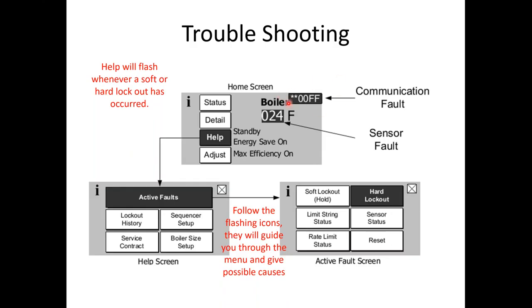But this one is a communication fault, and unfortunately, it's a 50-50 shot. It's either the control stopped talking to the display, or the display stopped talking to the control. In some rare occasions, it's the harness is loose. In some rare occasions, the harness, especially if it happens right out of the box in shipping, the green communication harness usually just needs to be plugged back in.